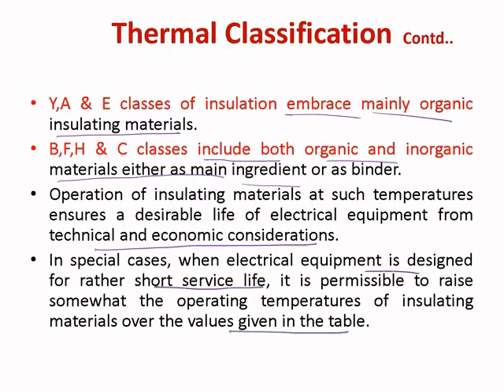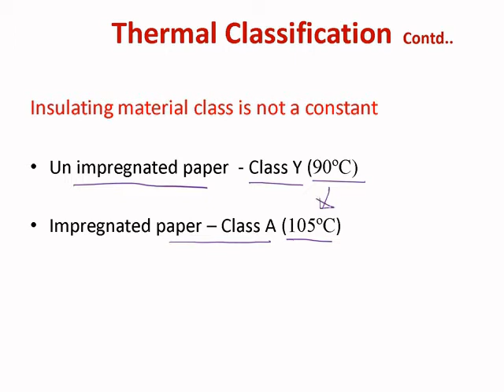Now, insulating material class is not a constant. Similar material can be used for a different class with some modification. Just for example, unimpregnated paper comes under class Y insulation, and maximum temperature withstand capability is 90 degrees centigrade. Whereas similar insulating material, that is paper, in impregnated condition is transferred from class Y to class A insulation, and maximum temperature withstand capability also increases from 90 degrees centigrade to 105 degrees centigrade.